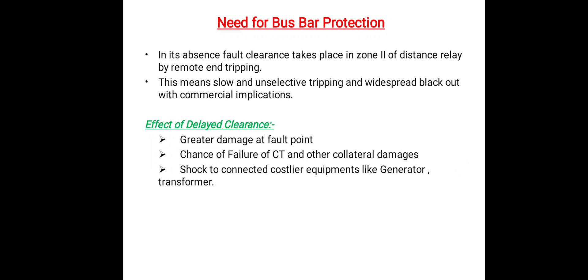What is the need for bus bar protection? Bus bar protection faults are rare, but if this fault occurs in our power system, considerable damage and disruption of supply will occur. In absence of bus bar protection, fault clearance takes more time because fault clearance will take place in zone 2 of distance relay by remote end tripping, meaning slow and unselective tripping and widespread blackout with commercial implications. The effects of delayed clearance include greater damage at the fault point, chance of failure of current transformer and other collateral damages, and shock to connected costly equipment like generators and transformers.